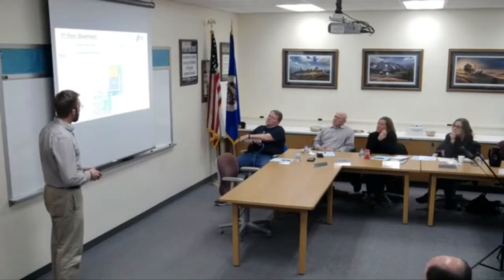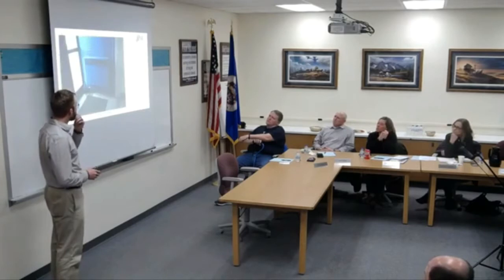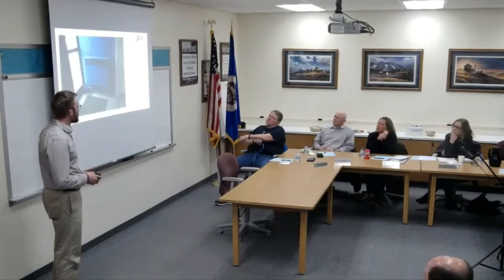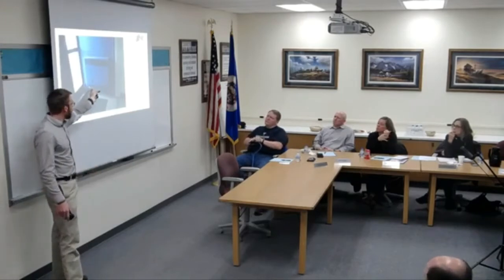Another space is the doors between the two locker rooms on the east side of the school. This is a steam cabinet unit, and it's got a perpetual leak on the fitting right down at the bottom. One of the things I noticed when I walked around is that there are no isolation or shut-off valves on any of the heating equipment.